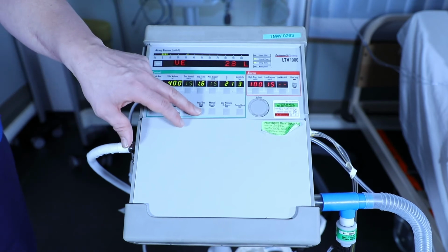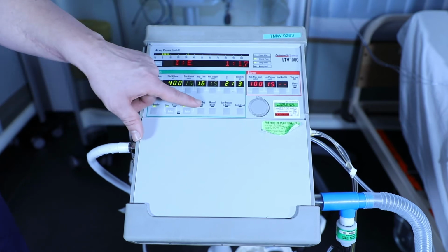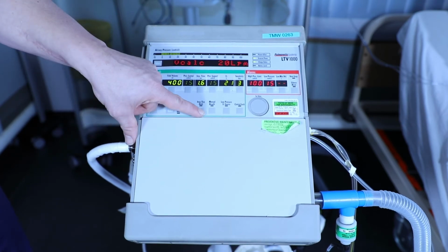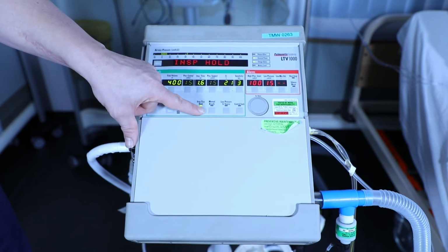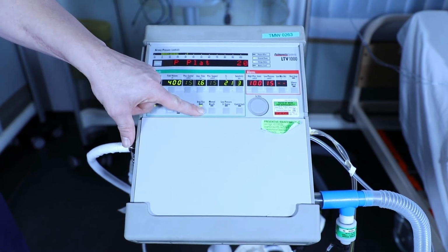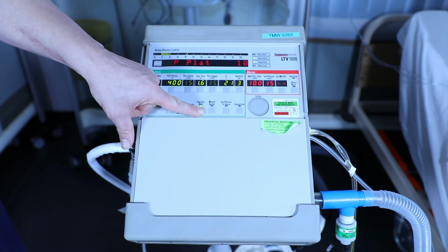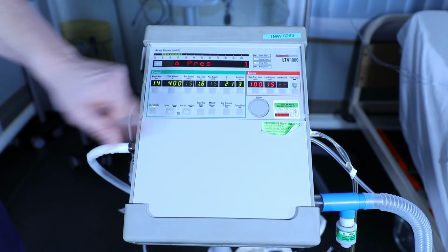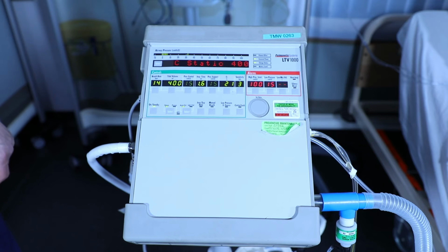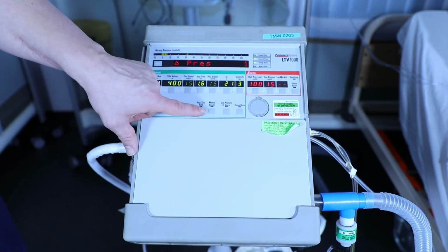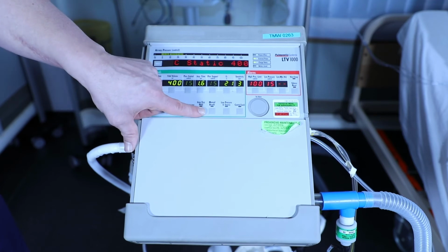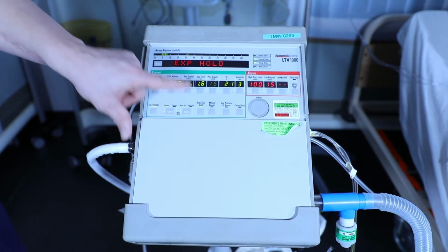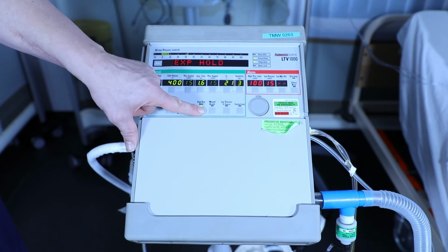We then have the inspiratory expiratory hold. Now, in order to give an inspiratory hold, we must be on a volume mode. So if I press this, we can see up here that it's selected inspiratory hold. Now press and hold, and we wait for the C static to appear on the screen, and that will determine that we've completed the full inspiratory hold. To complete an expiratory hold, we can be in volume or pressure, so we can press the inspiratory hold, press it again, now expiratory hold appears, and press and hold. And again, we'll know that this is complete when auto PEEP appears on the screen.